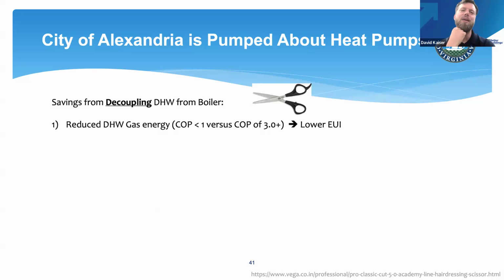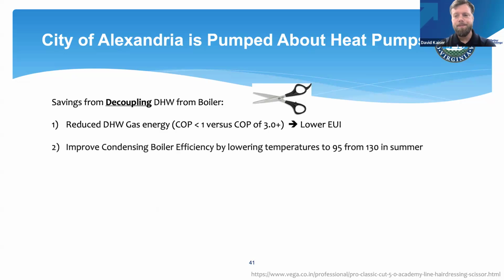separation, decoupling the domestic hot water heater from the boiler. Obviously, we're getting heat pump hot water heaters. So there is some energy savings just from the application of a heat pump, going from a COP of less than 1 to a COP of around 3, depending on the capacity of that system. Next, please.